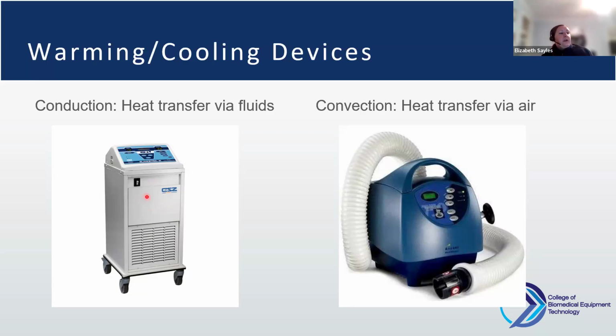So the Blanketrol 3, in terms of how it gets cleaned: one of the things, if you work on these devices, is you'll end up draining the water and running a bleach type cycle through, or hydrogen peroxide, depending on the manufacturer's recommendation, through these systems. Then check the pH once you've run the cleaning solution through a number of times, and then run regular water through it as well.